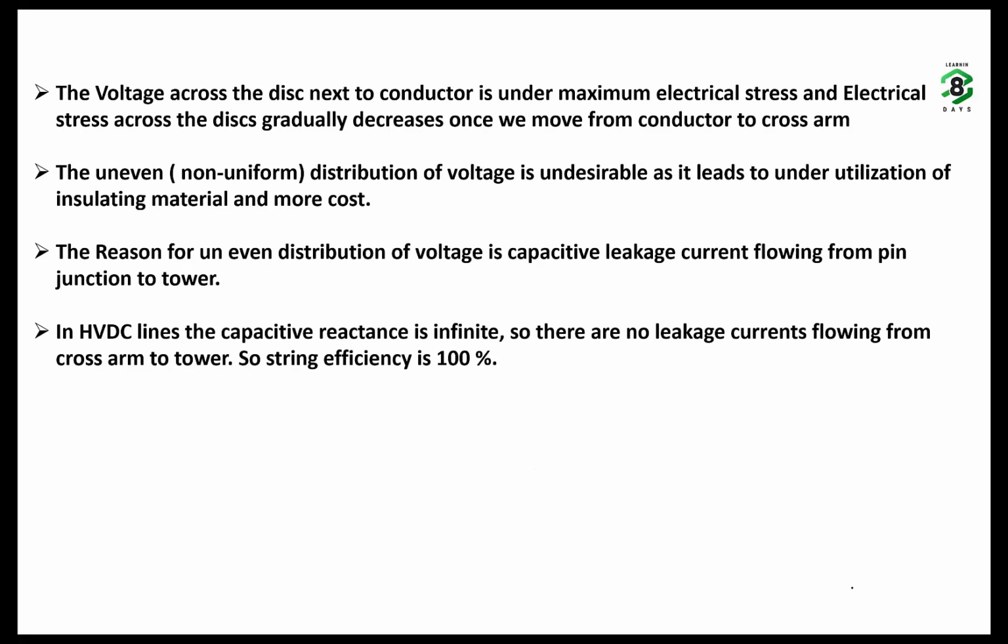Read one by one. Let some student read one after the other. The voltage across the disc next to the conductor is under maximum electrical stress, and electrical stress across the disc gradually decreases as we move from conductor to cross arm.